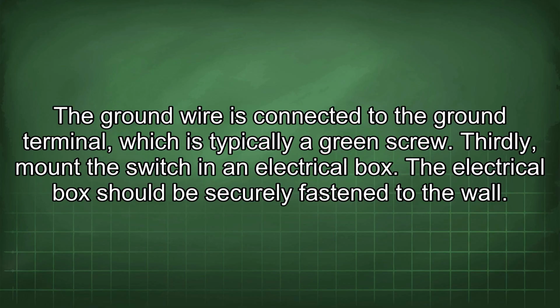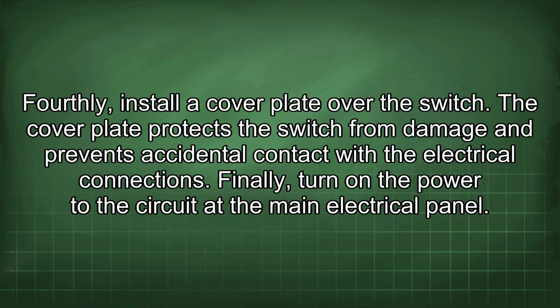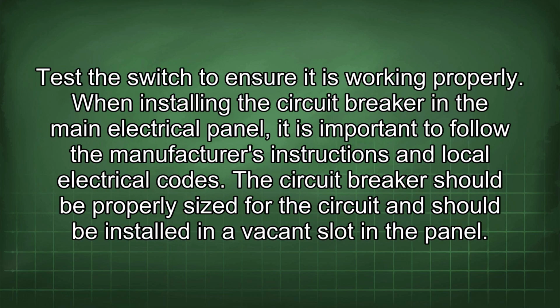Thirdly, mount the switch in an electrical box. The electrical box should be securely fastened to the wall. Fourthly, install a cover plate over the switch. The cover plate protects the switch from damage and prevents accidental contact with the electrical connections. Finally, turn on the power to the circuit at the main electrical panel. Test the switch to ensure it is working properly.